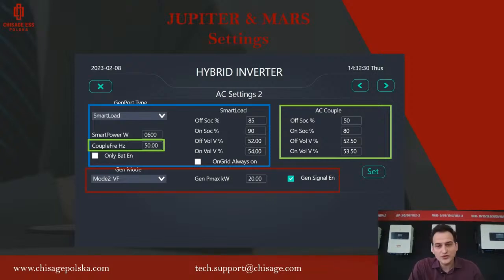And then we have on-grid always on. That means that the on-grid smart load will always be on. And on the left, we have only battery enabled. That means that whenever the battery is enabled, the inverter will power the smart load. And for the AC coupling, we have the green frame. So we have the state of charge for start and stop, and AC couple frequency on the left.